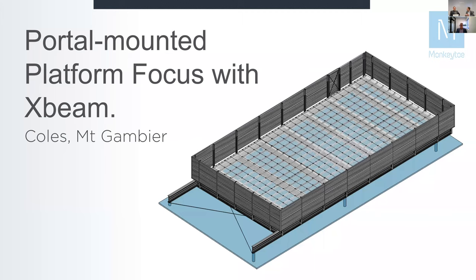A plant platform of that size manufactured out of structural steel the traditional way would weigh between five and twelve tonnes, which would be virtually impossible to install in that way. But X-Beam provided that solution. We provide a full detail from start to finish — certification, shop drawings, the product, supply, install, freight to site, the whole package. On this job it included the stubs from the structural steel right up through the roof, the platform itself, and the screening. We work with structural engineers and acoustic engineers to ensure the building structure is adequate to support the load we're putting on it.